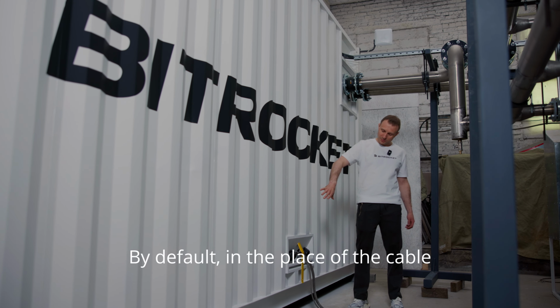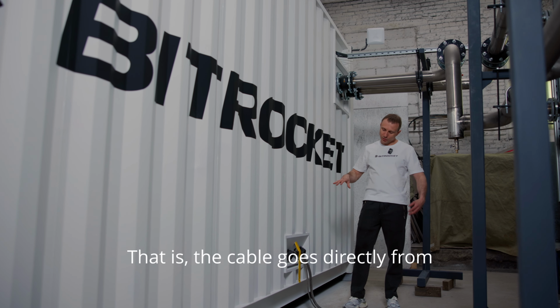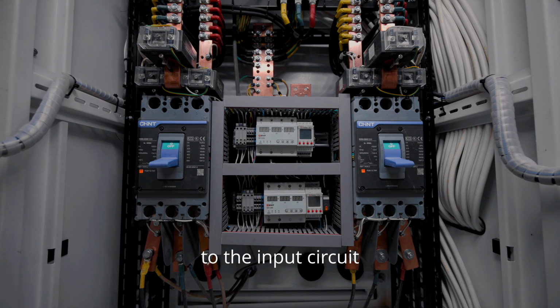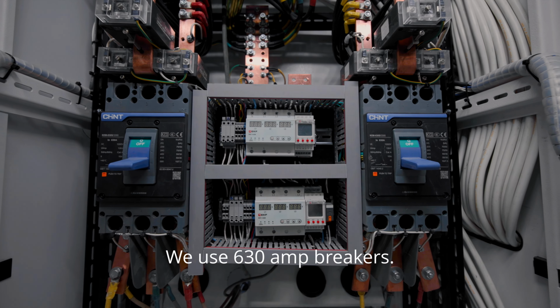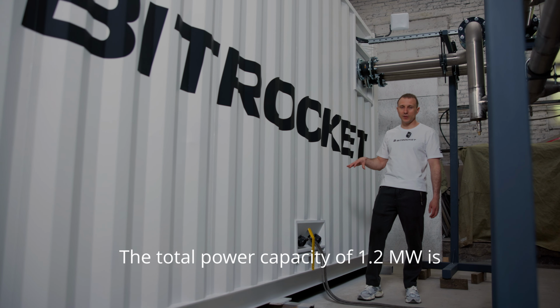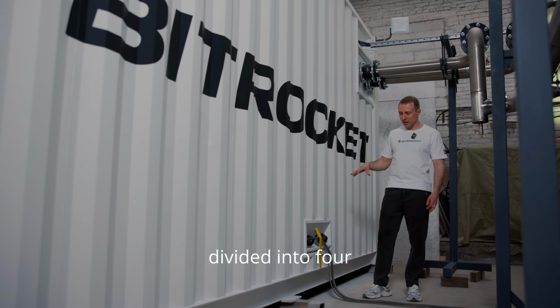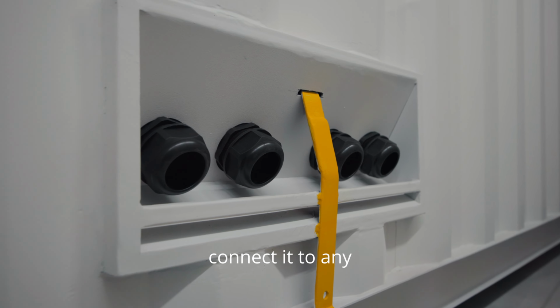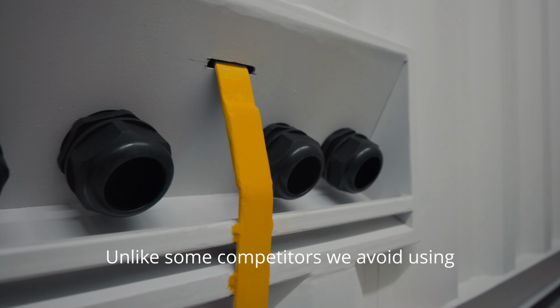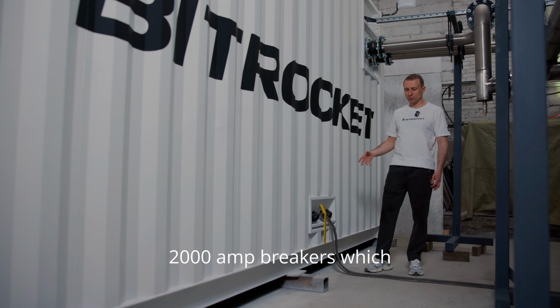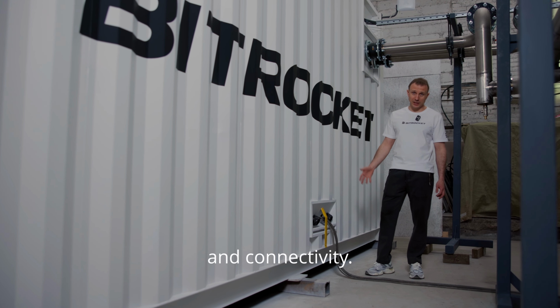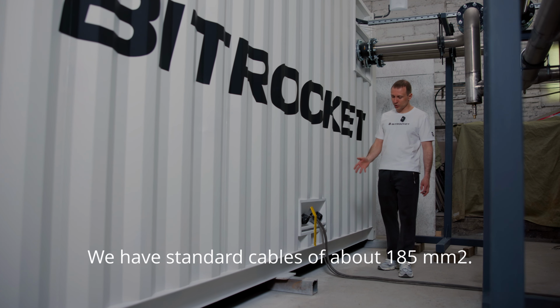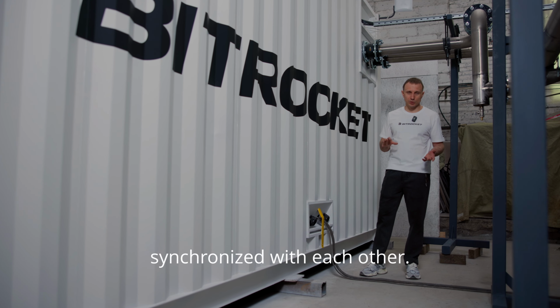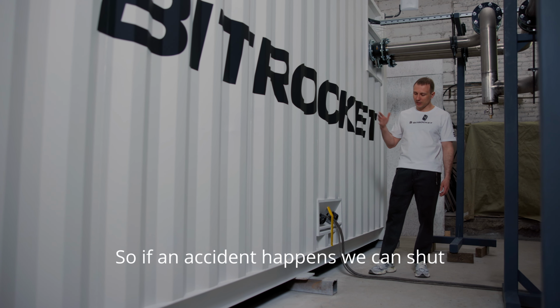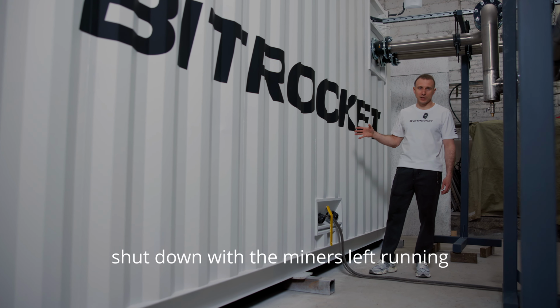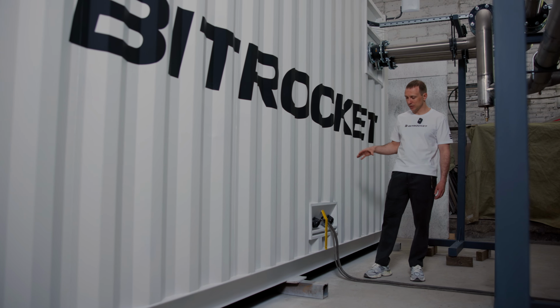By default, in the place of the cable input, we have a switchgear. That is, the cable goes directly from below into the switchgear to the input circuit breakers. We use 630 amp breakers. The total power capacity of 1.2 megawatts is divided into 4 separate inputs, so that you can connect it into any standard transformer substation. Unlike some competitors, we avoid using 2000 amp breakers, which can complicate installation and connectivity. We have standard cables of about 185 millimeters squared. The 4 inputs are synchronized with each other, so if an accident happens, we can shut them down synchronously so that the pump does not shut down with the miners left running without a coolant flow.